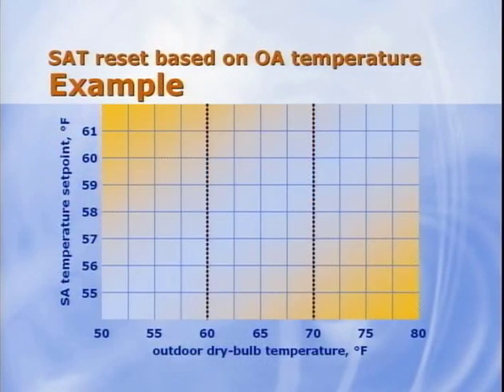This slide shows an example of a supply air reset strategy that is based on outdoor temperature. The reset high limit is set to 70 degrees Fahrenheit. When the outdoor dry bulb temperature is warmer than 70 degrees, no reset takes place, and the supply air set point remains at its design value of 55 degrees.